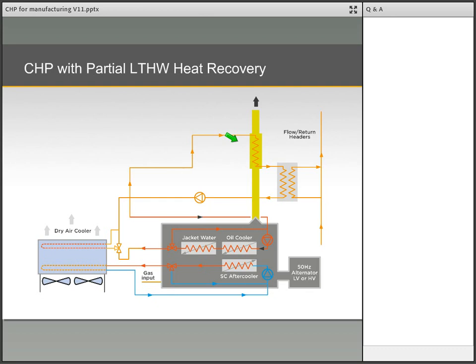Should the owner decide for financial or ecological reasons not to want to reject heat, an alternate control algorithm can be used. In this scenario, as the return temperature increases, the control system will downrate the output of the engine until either the return temperature stabilises or the engine reaches around 50% output, at which point it will undergo a controlled shutdown and wait for the return temperature to drop to the design condition. Whilst this system reduces the power and heat output of the CHP, it also reduces the amount of fuel required and thus maximises the system efficiency.